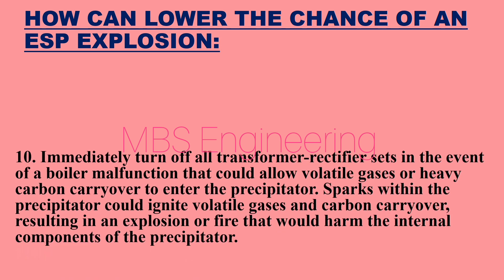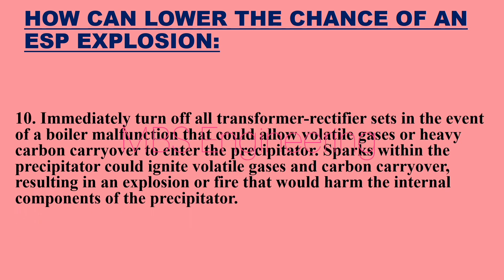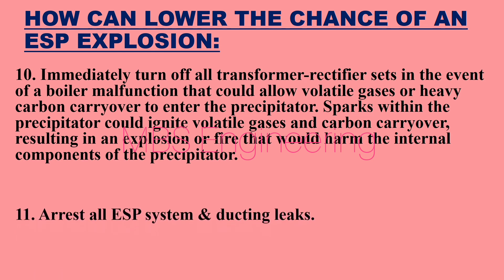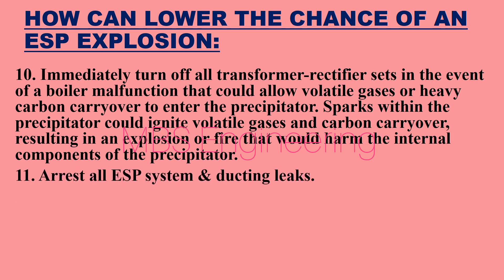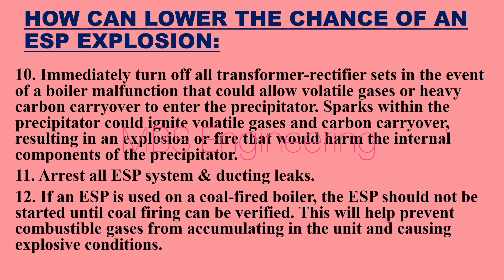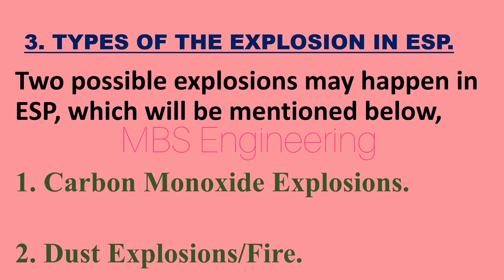Point 10: Immediately turn off all transformer rectifier sets in the event of a boiler malfunction that could allow volatile gases or heavy carbon carryover to enter the precipitator. Point 11: Arrest all ESP system and ducting leaks. Point 12: If an ESP is used on a coal-fired boiler, the ESP should not be started until coal firing can be verified. This will help prevent combustible gases from accumulating in the unit and causing explosive conditions.